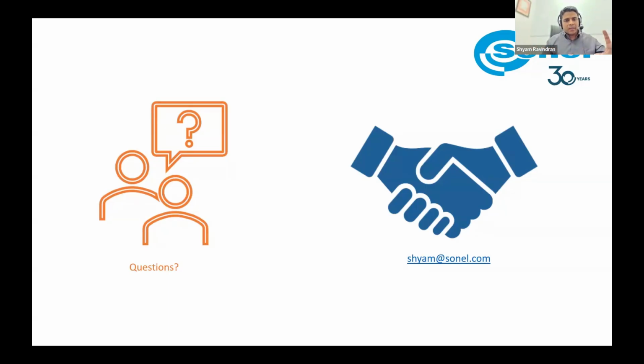If we can take the data out in a common format, for example a PQDIF format or a Comtrade format, tomorrow I can buy equipment from any manufacturer and still take the data out in that format. So legally speaking, if equipment has certification on Class A, and meets IEEE 519-2022 standards, you're not in a position to say no to that particular company. It can be any company.